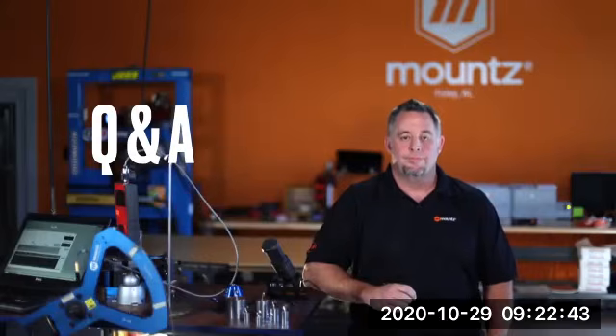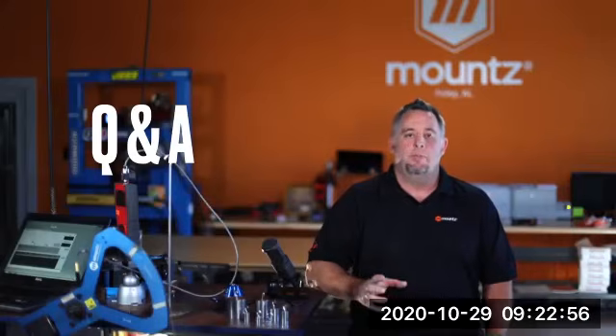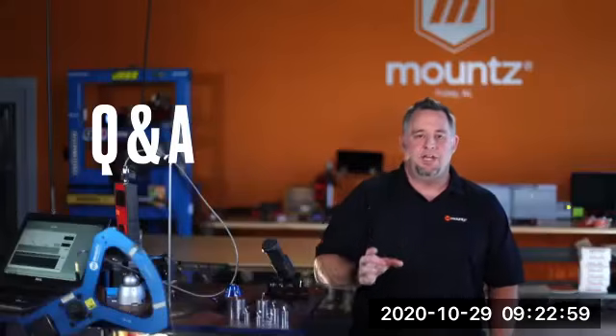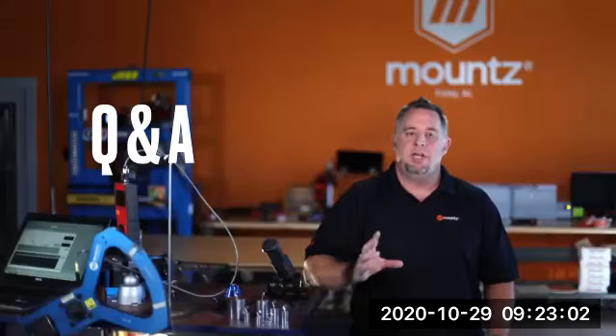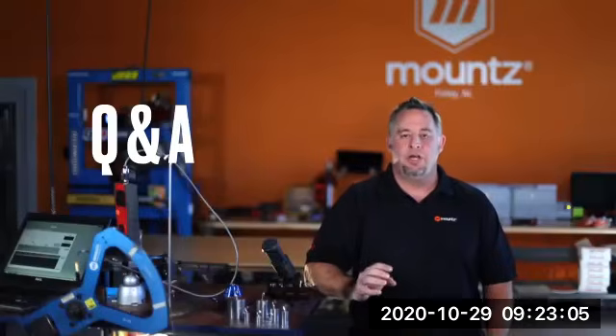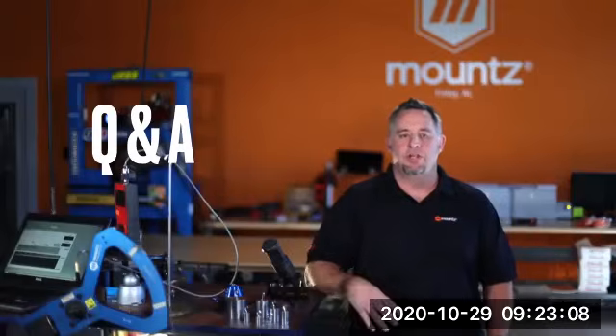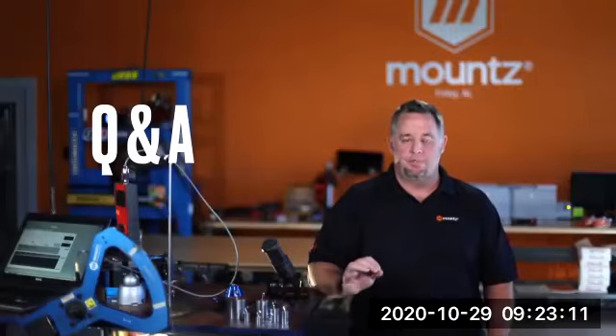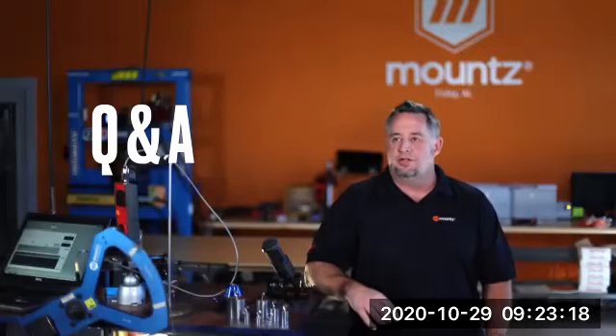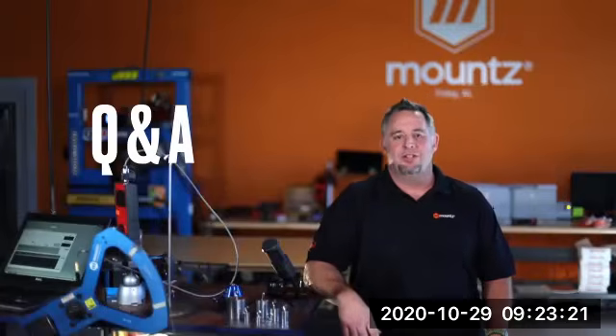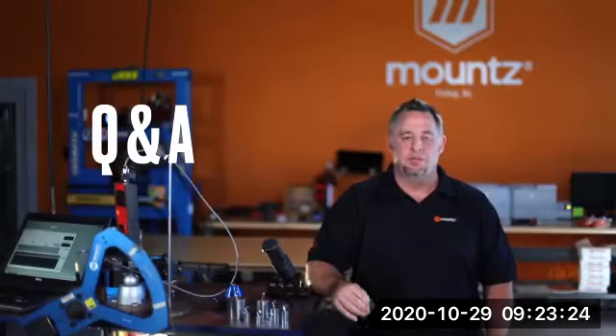I have a question from James. Does the PTT display have any effect on the calibration process, and would we still get the same results regardless of which PTT was used? Yes, the typical PTT and analyzer can be married as one particular unit. However, the calibration data for the sensor is stored on the automatic recognition chip within the transducer. So I conferred with our top crack team of calibration technicians, and they confirmed yes, it is possible to use a different PTT with a different sensor.